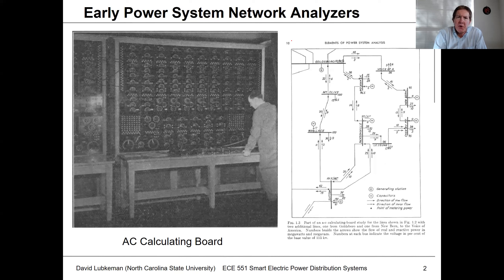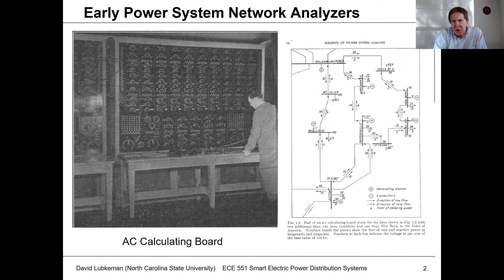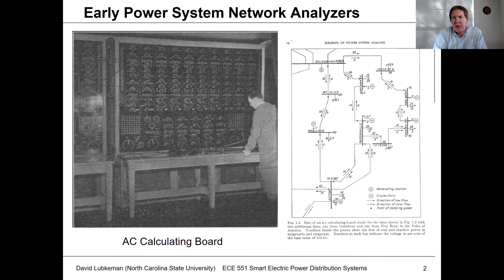You might scale voltages down to something like 120 volts or 12 volts AC. Then you would scale all the line impedances and transformer impedances so that when you got a value for current based on this 12 or 120 volt AC source and applied a scaling factor to it, it would correspond to the current you would have on the real system. In order to do something like this, for each transmission line segment you'd have to have a way of setting an equivalent resistance and reactance for the line.